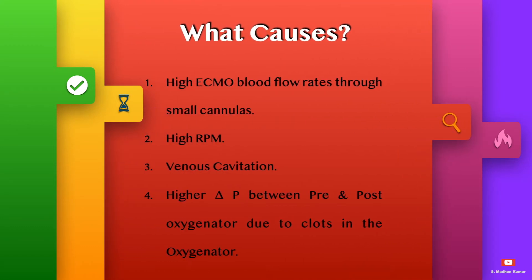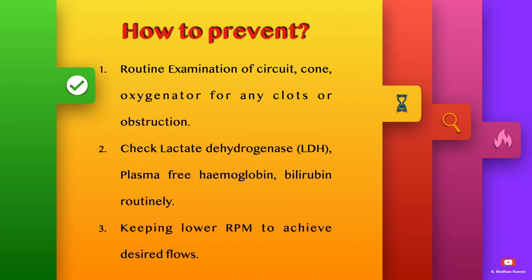Hemolysis can be caused due to high ECMO blood flow rates through smaller cannulas, high RPM, venous cavitation, and higher delta P maintained between pre and post oxygenator due to clots in the oxygenator.